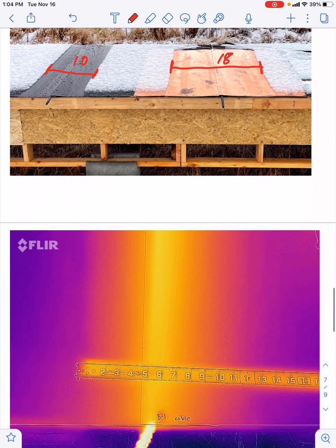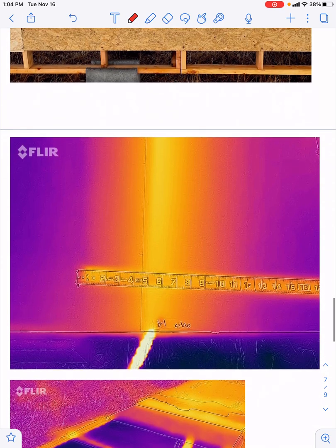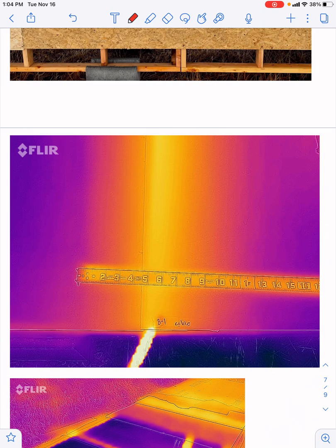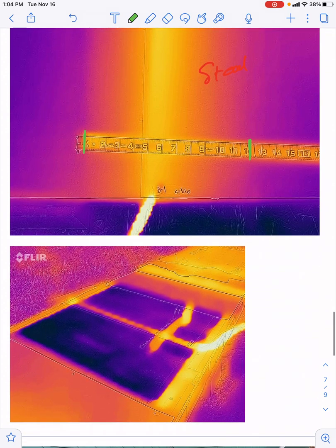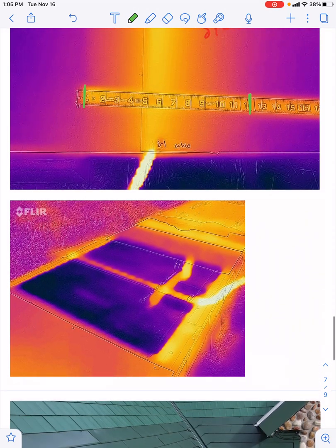And here's another couple of tidbits here on material. So when considering the type of material, this is steel right here. I should go to a green color here, but the heating contrast runs roughly 12 inches across for the steel. So our steel panels, we typically do them at 12 inches, not any bigger. If you go bigger, then you lose efficiency and you're gonna be clearing less area and you could run into cold spots. But in exploring the different types of material, we decided to try aluminum.